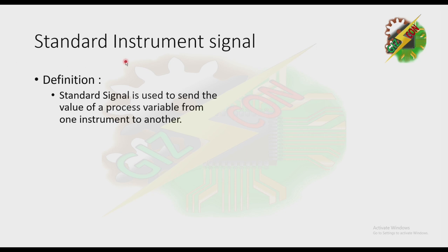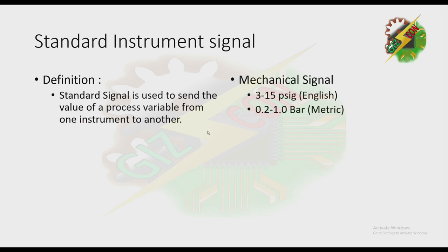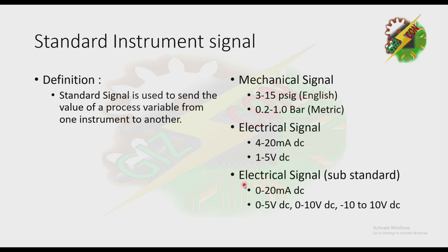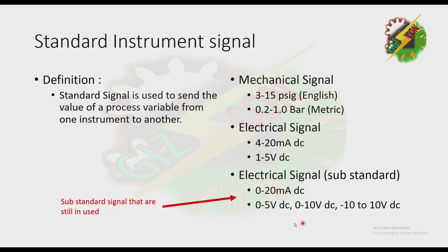Now let's discuss about standard instrument signal. By definition, a standard signal is used to send the value of the process variable from one instrument to another. For standard mechanical signal, we have 3 to 15 PSIG for the English system and 0.2 to 1.0 bar for the metric system. For standard electrical signal, we have 4 to 20 milliampere DC and 1 to 5 volts DC. We also have substandard electrical signals: 0 to 20 milliampere, 0 to 5 volts, 0 to 10 volts, and negative 10 to 10 volts. These are substandard but still used on some instruments.